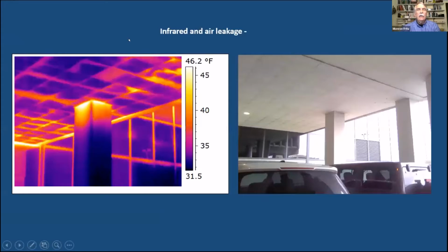So here's what air leakage can look like to infrared. Now we have a very strange building here, and you will see the proverbial suspended ceiling and the digital image on the right. And this is very odd that they would have in a semi-outdoor space have a suspended ceiling like that. But some architect who wasn't quite on his game when he designed this building put that in that situation and then went on top of that suspended ceiling and piled insulation on it. So he was expecting that suspended ceiling to act as an air barrier.